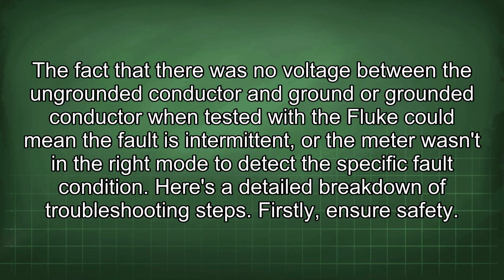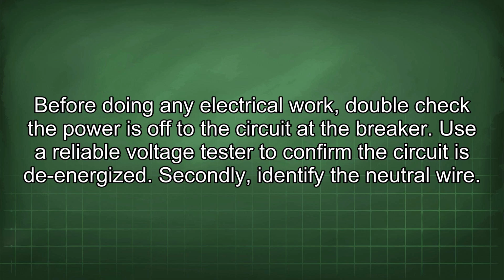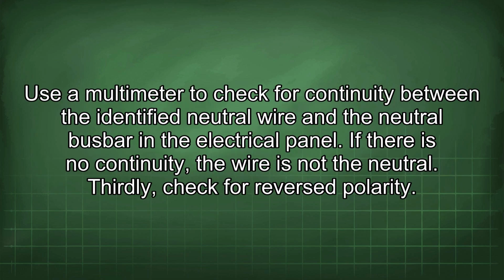Firstly, ensure safety. Before doing any electrical work, double-check the power is off to the circuit at the breaker. Use a reliable voltage tester to confirm the circuit is de-energized. Secondly, identify the neutral wire. Use a multimeter to check for continuity between the identified neutral wire and the neutral busbar in the electrical panel. If there is no continuity, the wire is not the neutral.